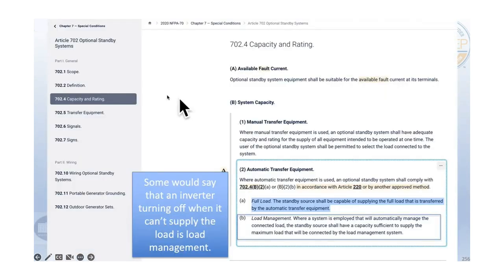And so let me just kind of say here, we go to Article 702. If we use an automatic transfer switch, it says that we need to power the full load or have load management. Powering the full load is not what we're going to do. We're not going to be able to power a 200 amp service with a 200 amp energy storage system or something like that. We don't do that. But another thing they figured out is load management.